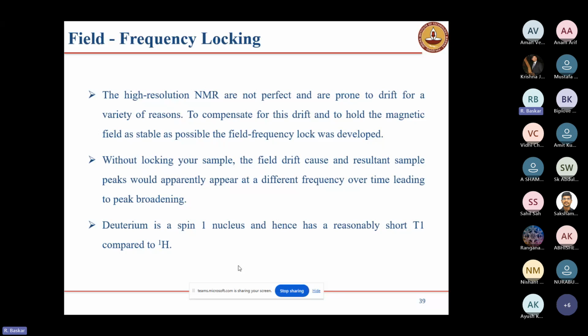Okay, what does locking mean? The magnetic field is very high. Already I told you that at 500 megahertz, the field strength is 11.742 Tesla. 1 Tesla equals 10,000 Gauss. Already I told you that over a longer time, at the ppm level, the magnetic field drift will be there. It may be higher or lower. If we haven't locked, when we are doing proton NMR, we'll get broader signals, because the field drift will always be there. A small drift will be there.